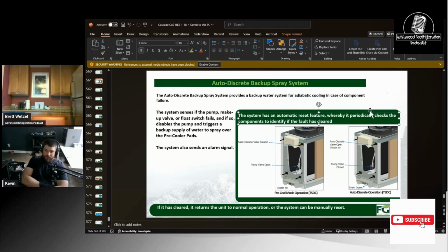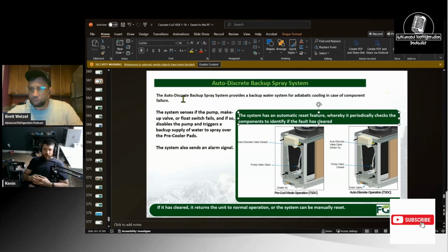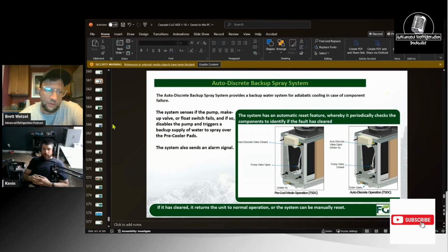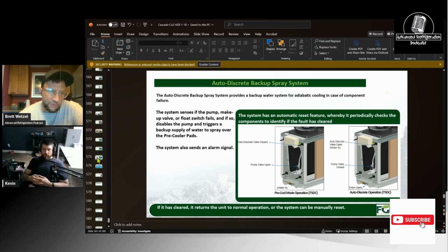But yeah, other than these, the BAC gas coolers are relatively simple. There's not a ton of programming going on in the background. The only thing that gets weird is the motors are communicating with the controller for their speed over Modbus. That's where it gets a little convoluted and a little more difficult to troubleshoot.